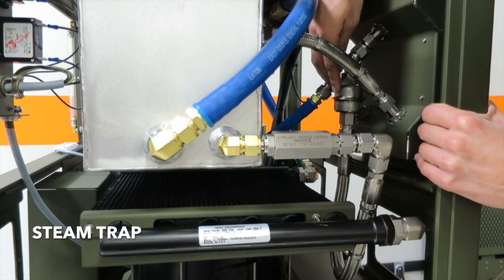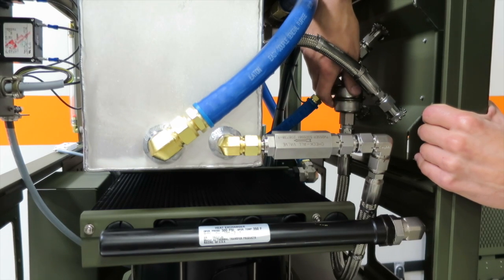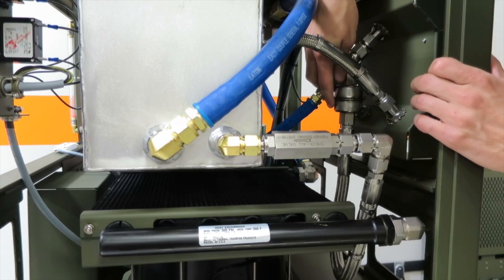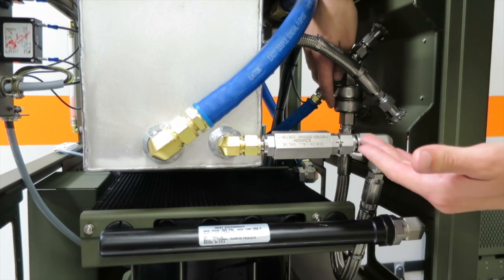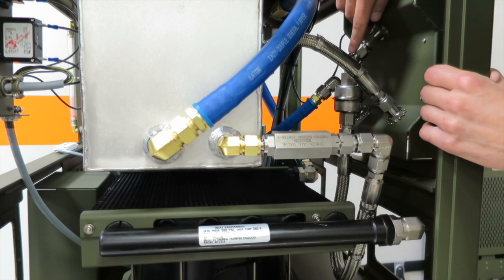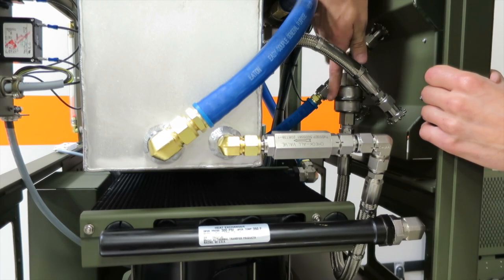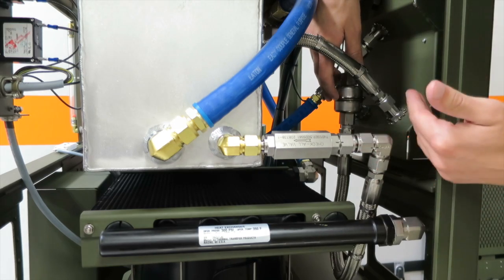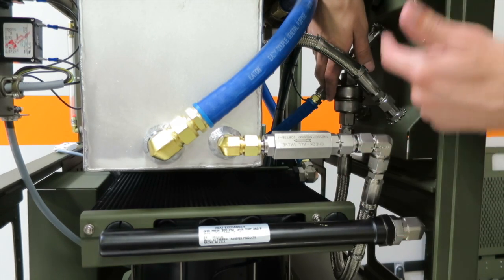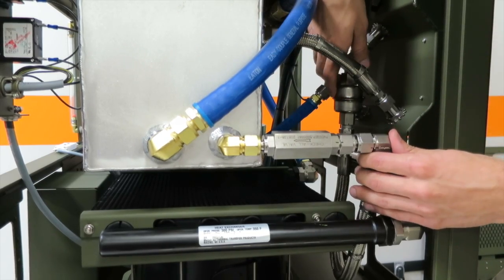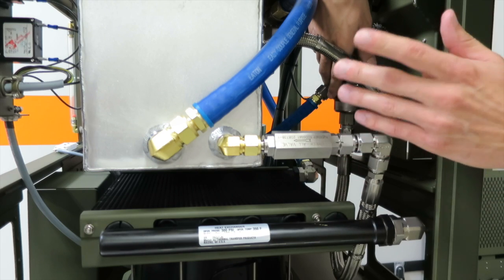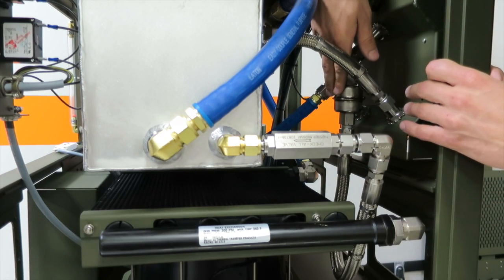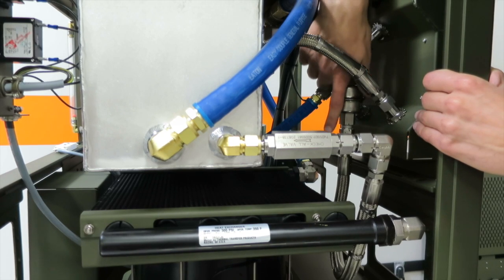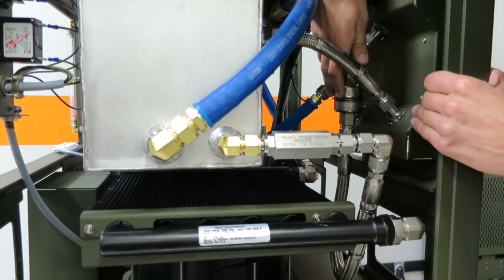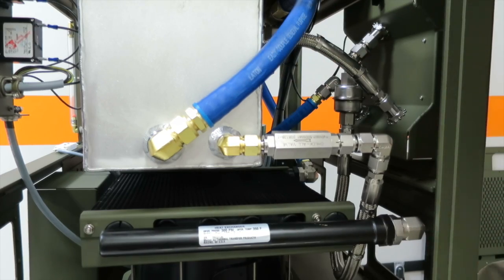What happens is when steam hits it, it expands the bellows and it seals off. So it allows the chamber to keep pressure. When condensation flows down out of the chamber and hits the steam trap, it cools those bellows off and allows them to open, and it allows the condensation to flow through back into the water tank. So whenever you hear some chattering, a little bit of noise throughout a cycle, that's the steam trap opening and closing and letting condensation through and then sealing back up when the steam hits it. So that's the steam trap.